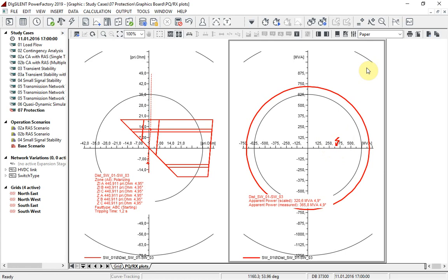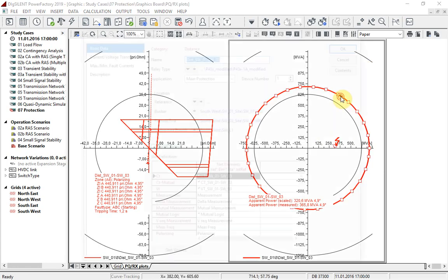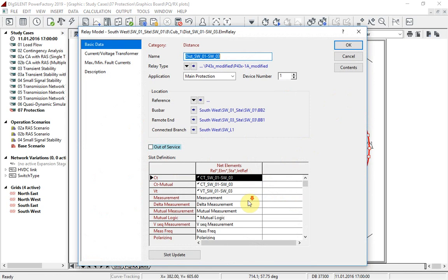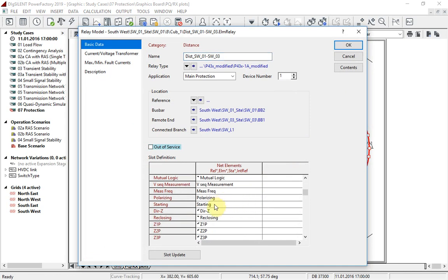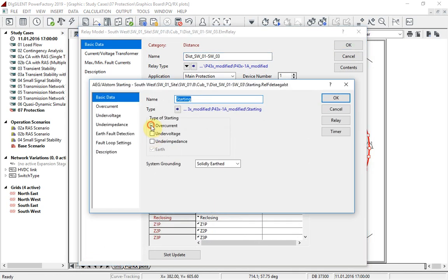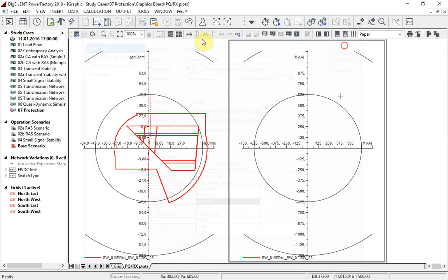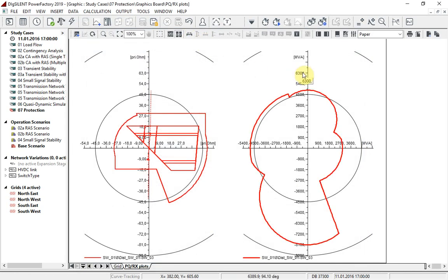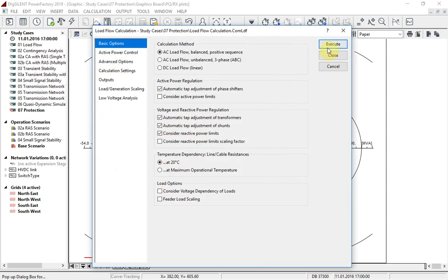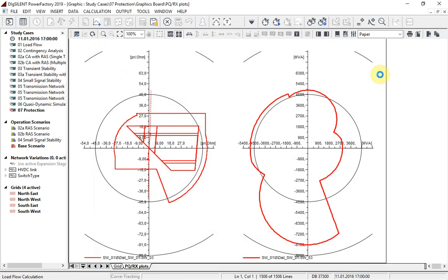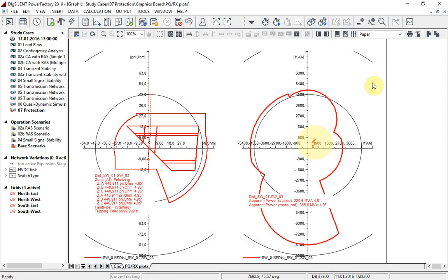Of course, the other starting types, such as impedance starting, are also supported. If we change to impedance starting, we see that it is likewise transformed into the PQ plane, and again we can run the load flow to see whether the operation point lies within the area of the characteristic.